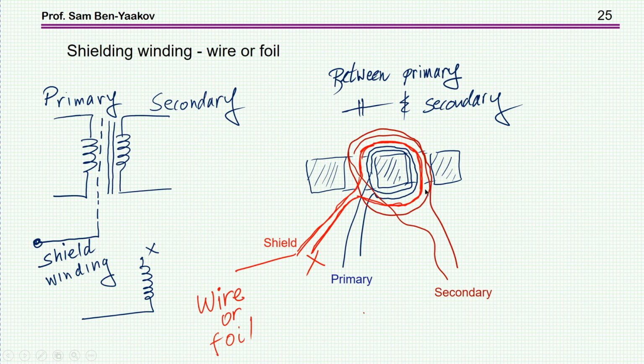How can we remedy this? One way would be to put a shield between the primary and secondary. The function of this shield is to block the electric field between these two, essentially eliminating the capacitance between the primary and secondary. The shield could be an extra winding with wires or foil, foil would be better. This extra winding is connected only on one side, the other side is left open, you don't connect anything to it.